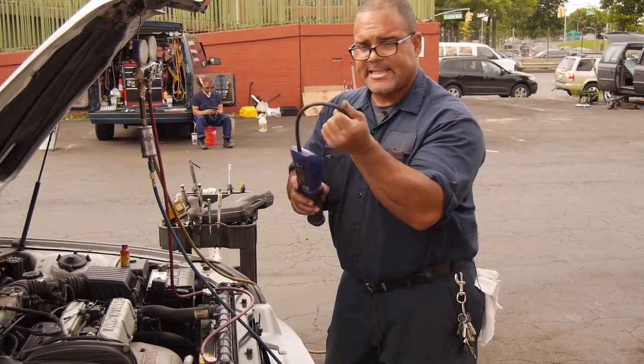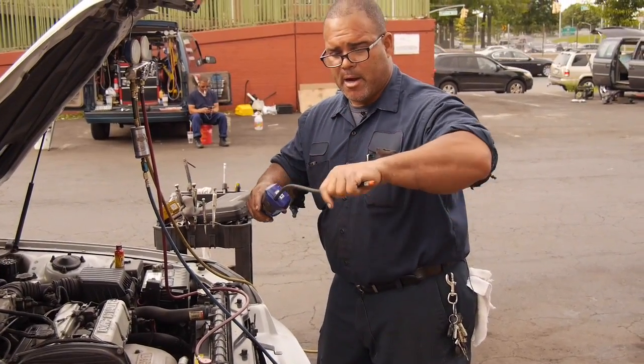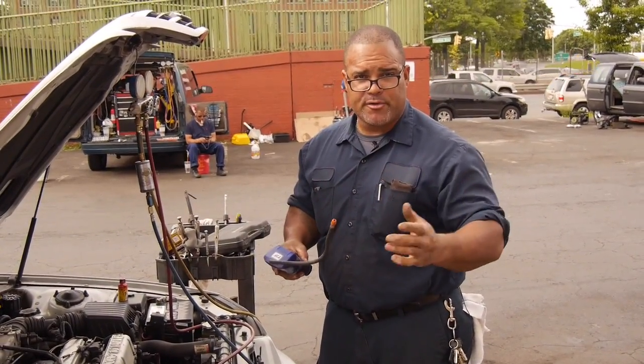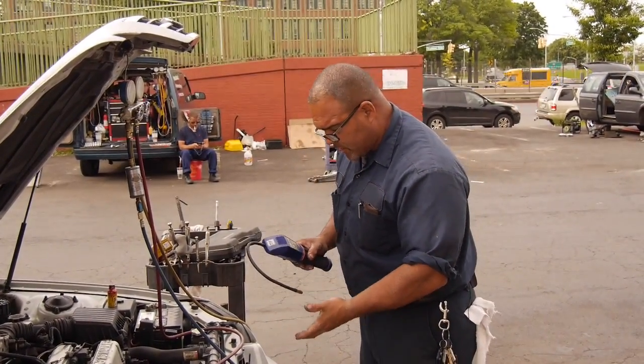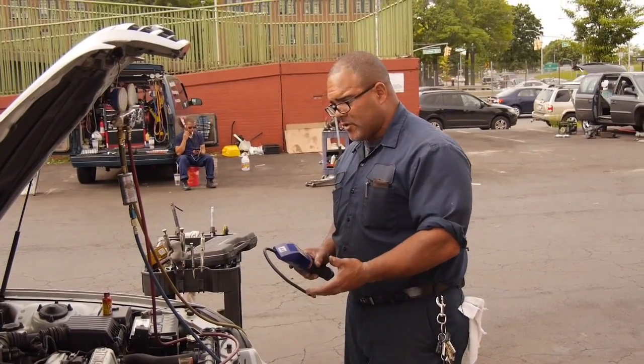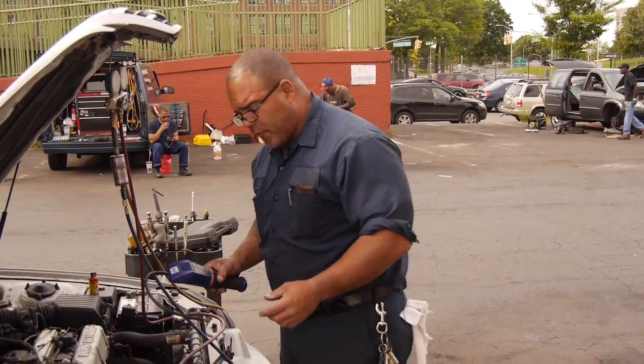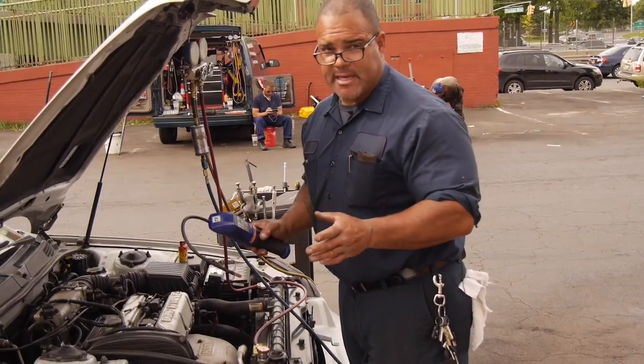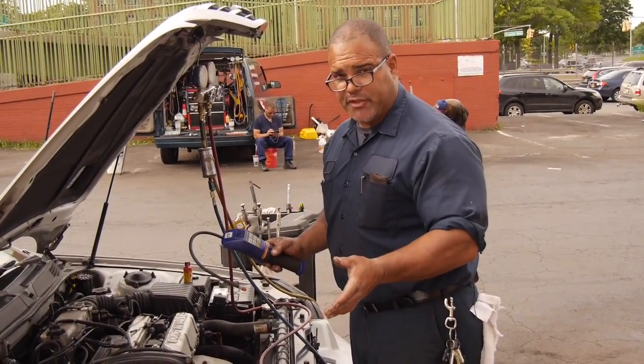You might have a line that's kinked, or a bent line where it's not flowing right. You got to look at your condenser, you got to look at the whole system. So far, so good, we haven't detected any leaks. That's a good thing for the customer.